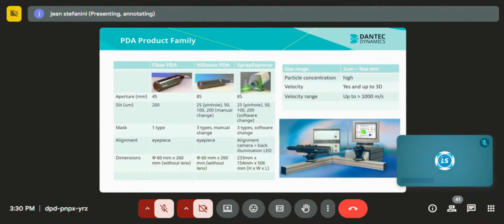In addition to the LDA, we have another product family which is called PDA, which stands for phase Doppler anemometry. If you recall, LDA measures velocity; PDA is going to measure size on top of velocity. In LDA you are using only one single probe that transmits the beam and collects the light back. PDA requires an additional probe, a receiver that contains only receiving optics. Every time a particle passes through the measuring volume, you will be able to characterize the size and the velocity.